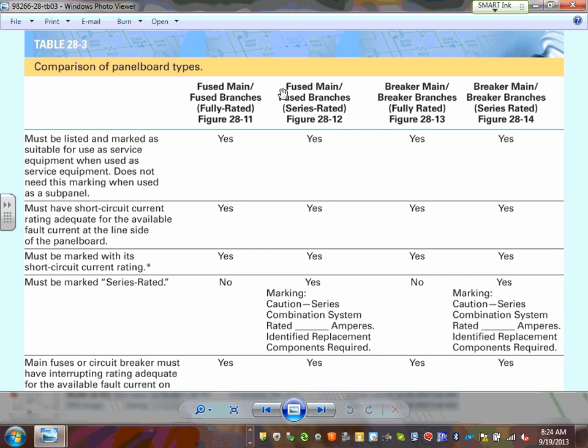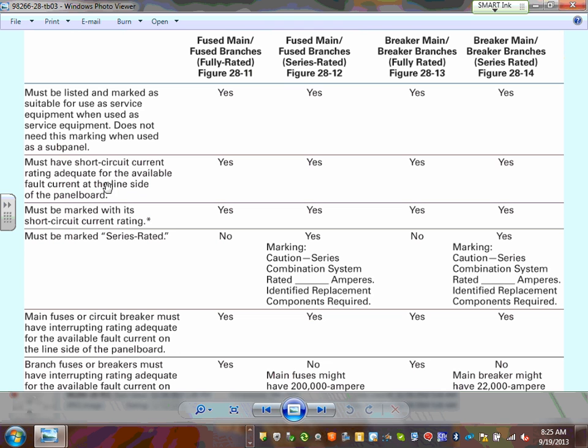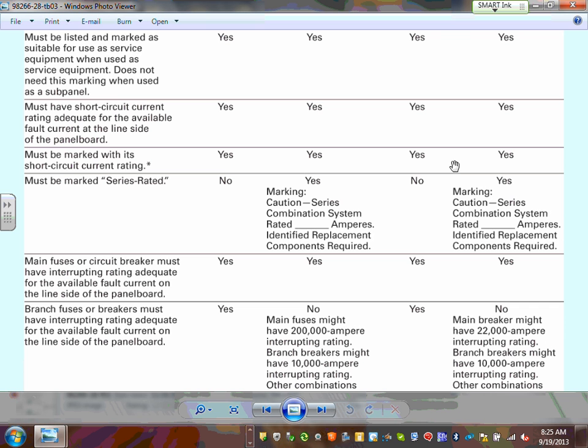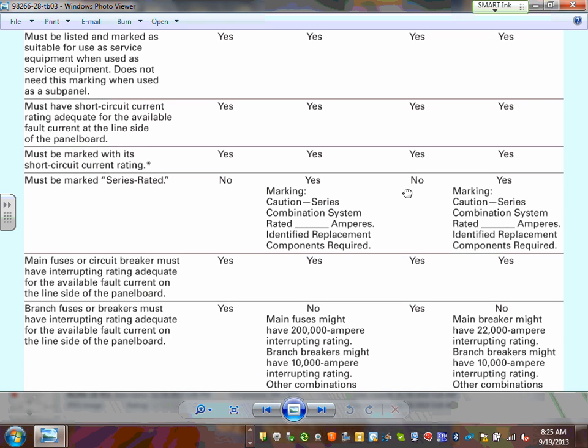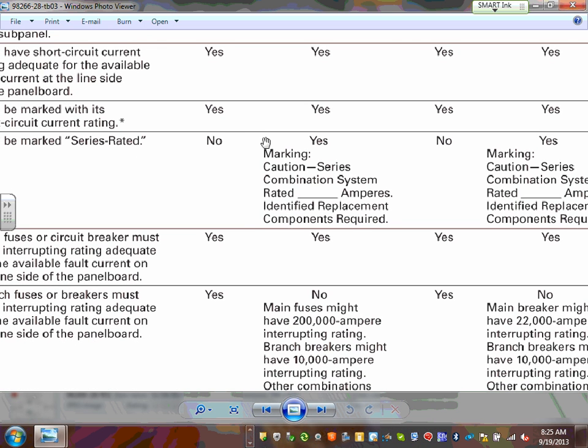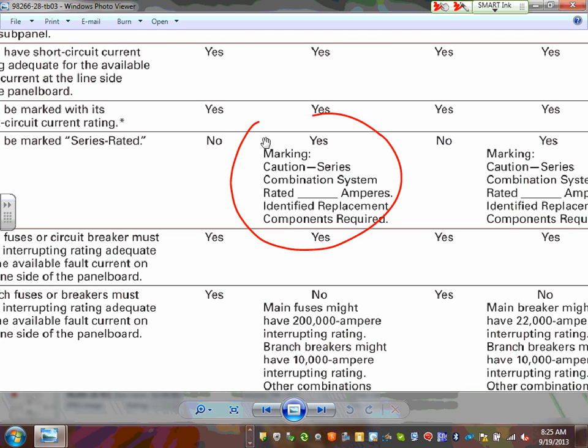All panels must be listed, regardless of whether they are fully rated or series rated. They must have an adequate short circuit current rating for the available fault current, and must be marked with the available short circuit current. If your panel is series rated, you must have a caution label stating 'series rated' or 'combination series rated,' identifying the replacement components required.